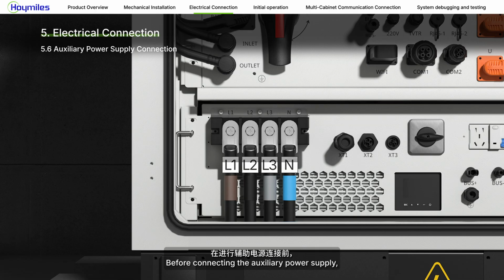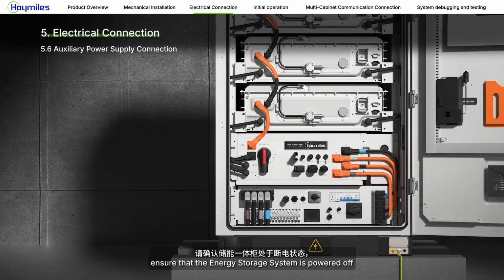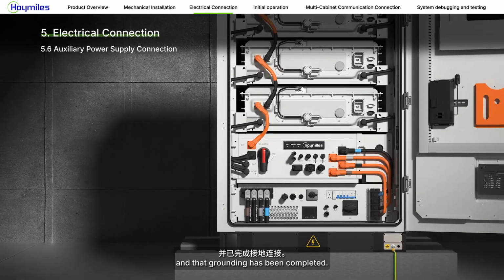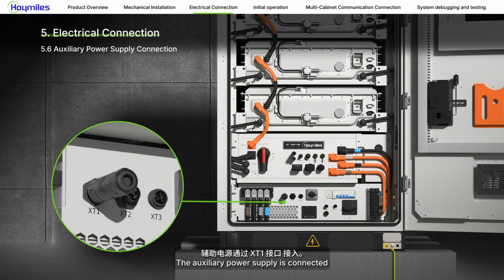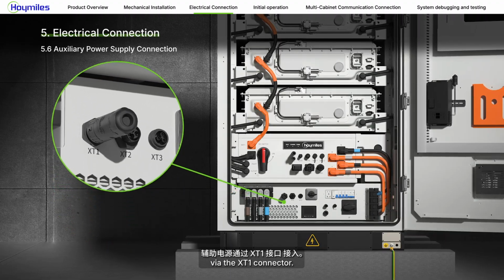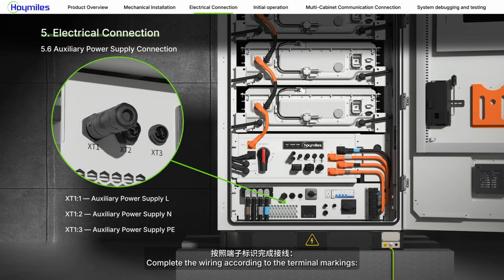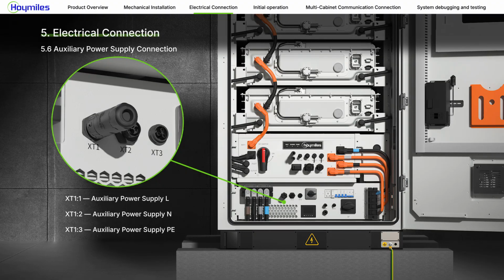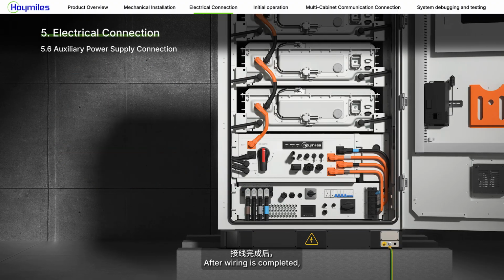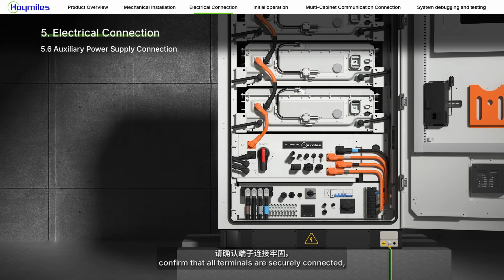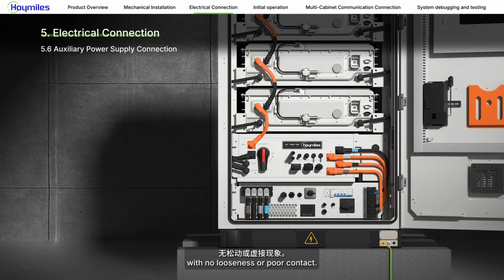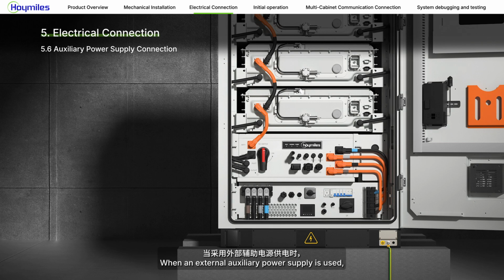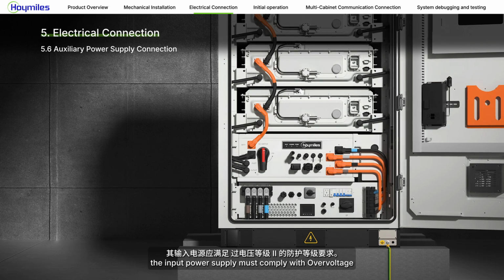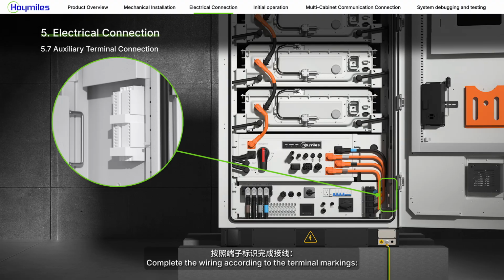Before connecting the auxiliary power supply, ensure that the energy storage system is powered off and that grounding has been completed. The auxiliary power supply is connected via the XT1 connector. Complete the wiring according to the terminal markings. After wiring is completed, confirm that all terminals are securely connected, with no looseness or poor contact. When an external auxiliary power supply is used, the input power supply must comply with overvoltage category 2 requirements. Complete the wiring according to the terminal markings.